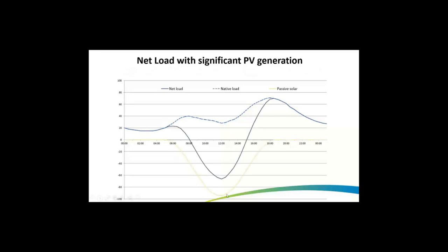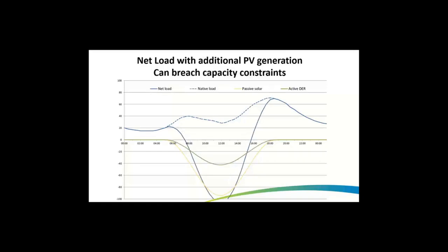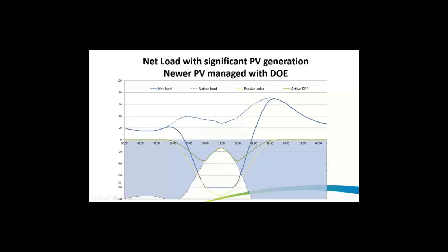Over the last decade, we've seen a growing amount of PV installed on these networks. We've seen the net load through our network reverse as a result of the PV generation in yellow. If we allow ongoing installations of PV, we eventually can breach the limits, for example, at minus 100% of the network. And so to manage this and minimize this occurring, we implement a dynamic operating envelope, shaded in blue here.